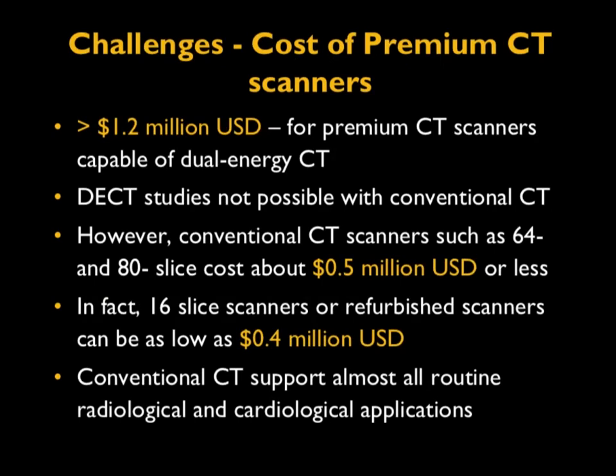Regarding the cost of premium CT scanners, those capable of dual energy CT can cost greater than $1 to $1.2 million. Dual energy CT is not possible with conventional CT without doing two scans, which increases radiation dose exposure to the patient — another factor limiting wider use.